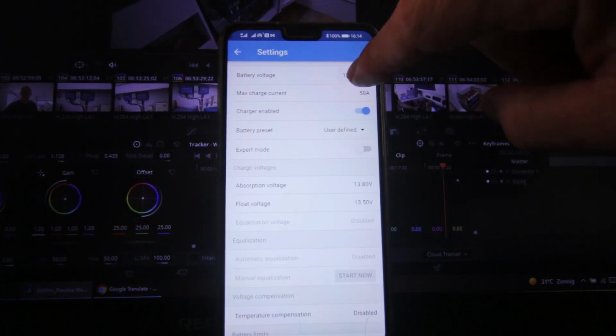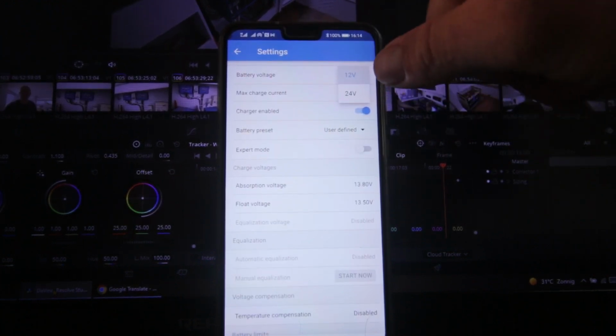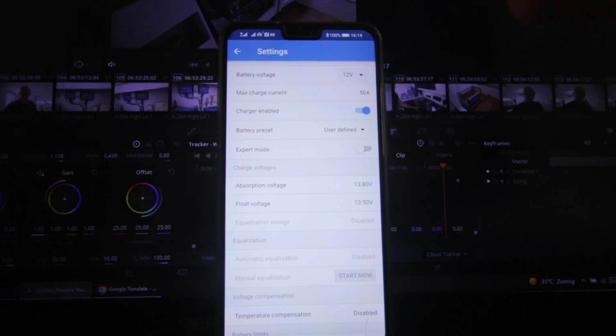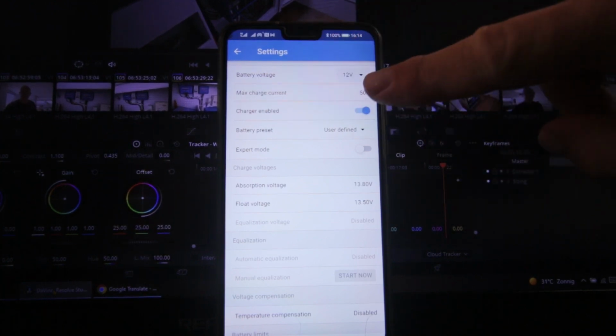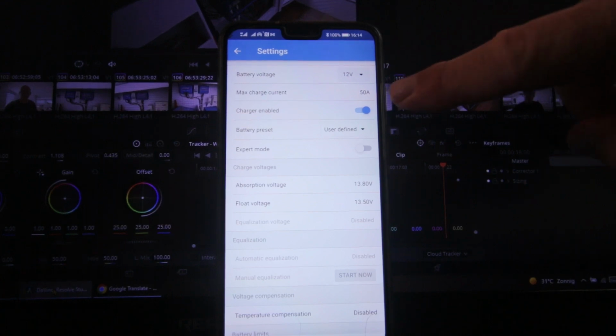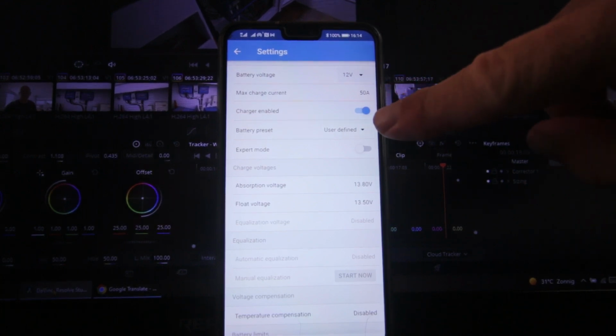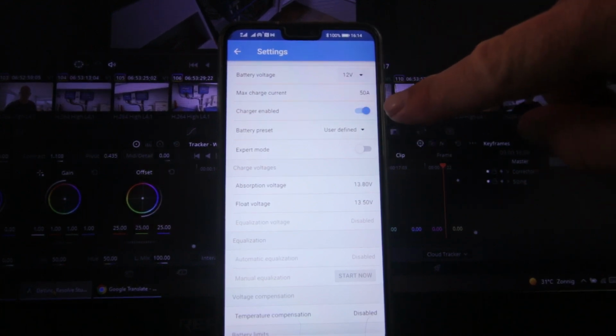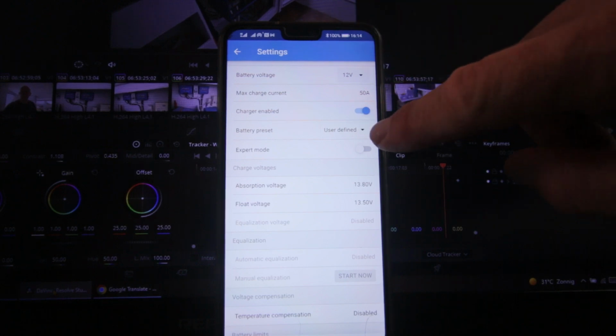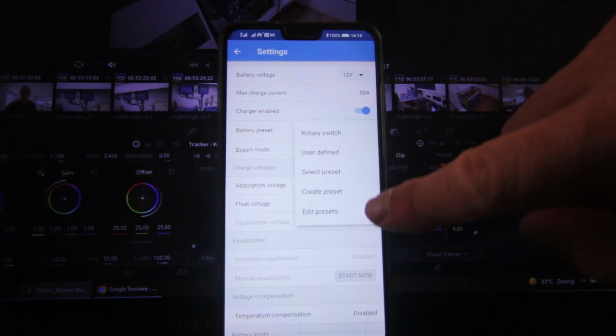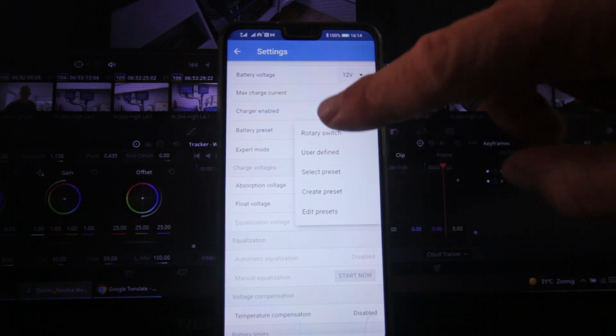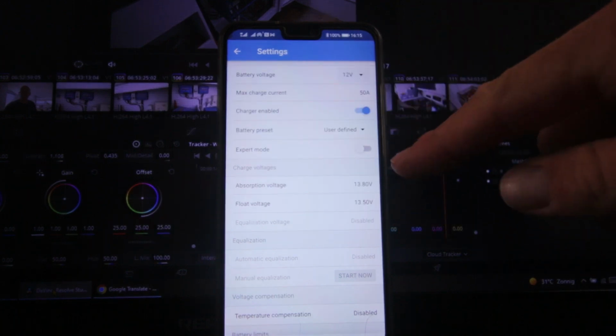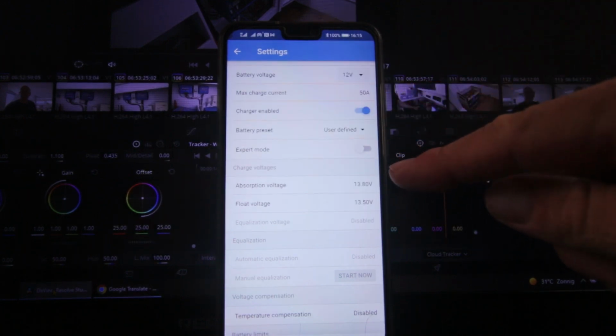Battery voltage, you can choose between 12 volt or 24 volt. Of course we have 12 volt, so that's clear. Maximum charge current, I think it will never go above 40, so 50 is okay. Charger enabled. Battery preset is user defined, so you can choose some presets or whatever, but because we want certain settings, it's user defined for us.